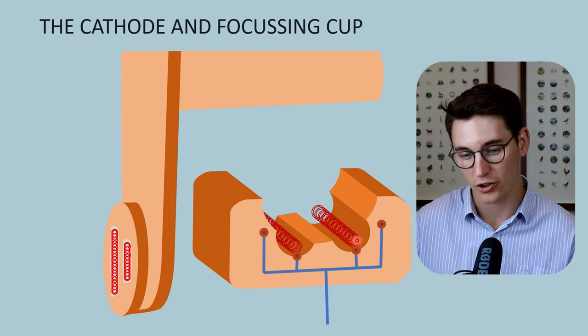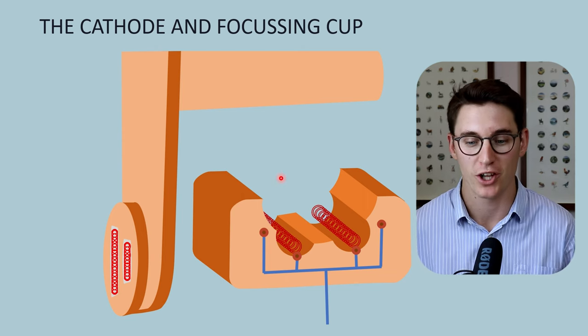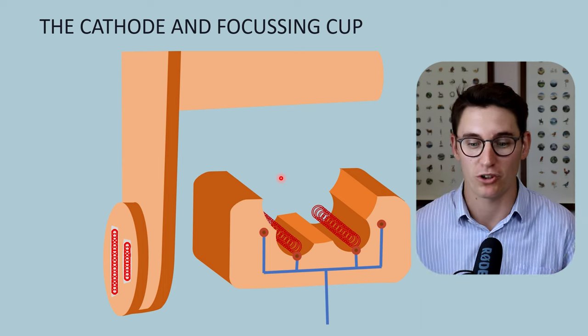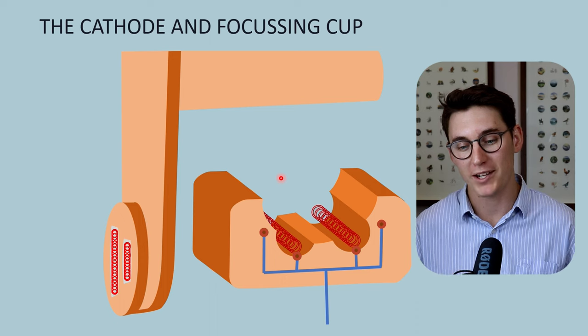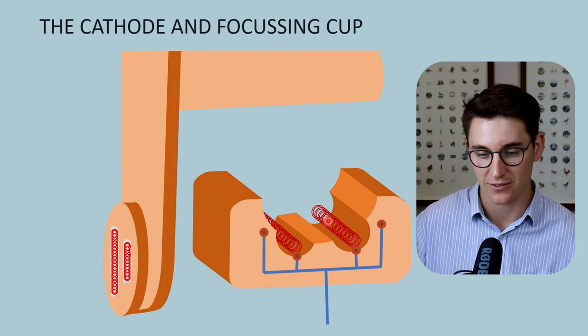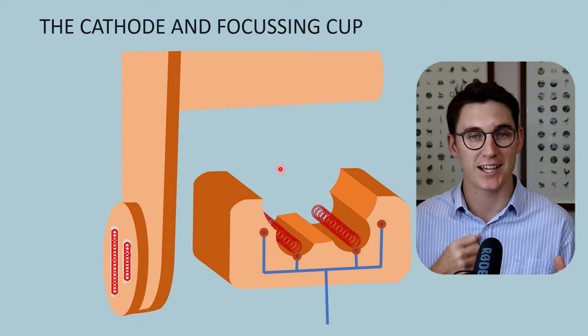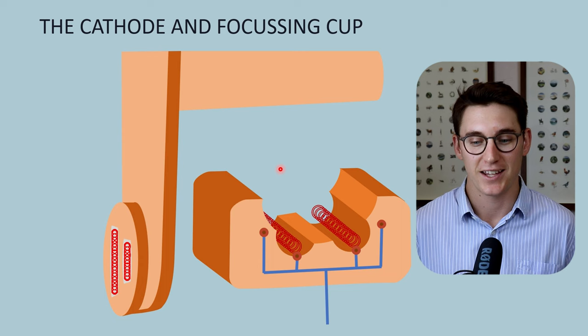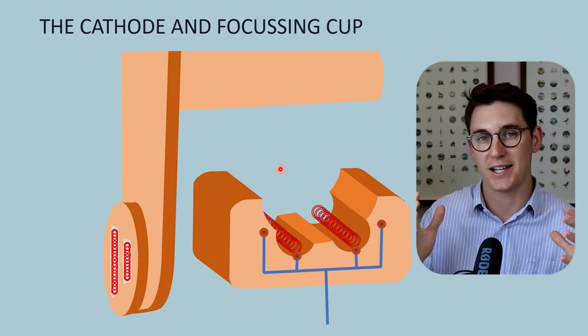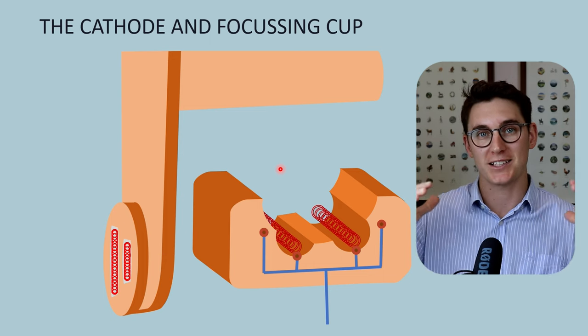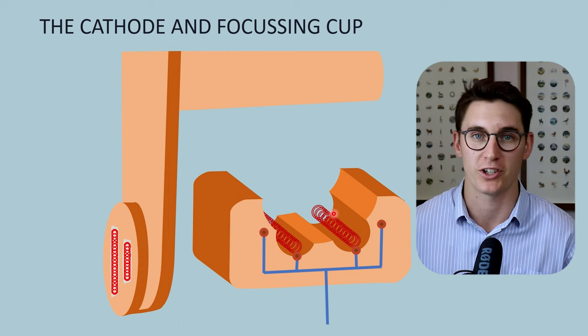We produce electrons on the surface of our tungsten filament coil through a process called thermionic emission — the emission of electrons due to heat. We run a current through this tungsten filament coil. The tungsten filament itself has high electrical resistance, and that current running through it will generate heat. The tungsten filament coil will heat up more and more, and that heat energy will allow valence electrons in our tungsten atoms to become excited, to go to the surface of the tungsten filament coil. That process is called thermionic emission.